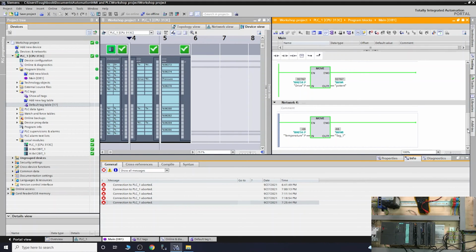Ladies and gentlemen, our input 1 is faulty on our 1KF02 analog card, at least the potential, the PT100 part of it. As you can see, my number should be showing roughly 220, 230, and as you can see, it's fluctuating and it's somewhere in the minus. This looks like we have a faulty channel.